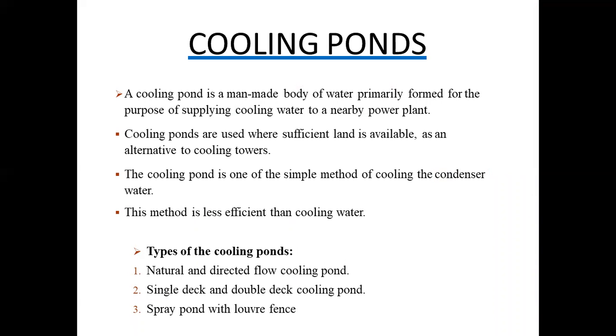Now, cooling pond. A cooling pond is a man-made body of water primarily formed for the purpose of supplying cooling water to a nearby power plant. Cooling ponds are used where sufficient land is available. It is an alternative to cooling towers. Cooling pond is one of the simple methods of cooling the condenser water plant. This method is less efficient than cooling tower, but it can be used where the soil capacity is not good, where we cannot erect cooling tower due to soil bearing capacity.